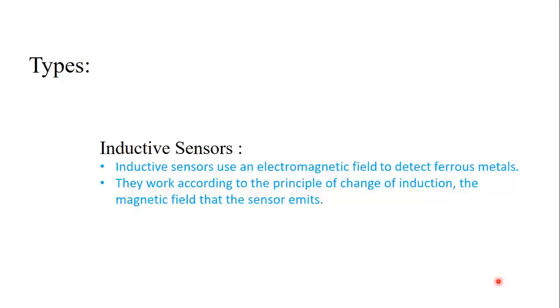The first one is the inductive sensor. Inductive sensors are used for the detection of metallic objects. If there is any metallic object nearby, the inductive sensor has a magnetic field around it. If a metallic object comes near, it causes a change in the magnetic field, and this change of induction allows the inductive sensor to sense that object.